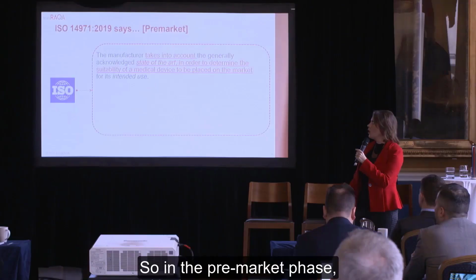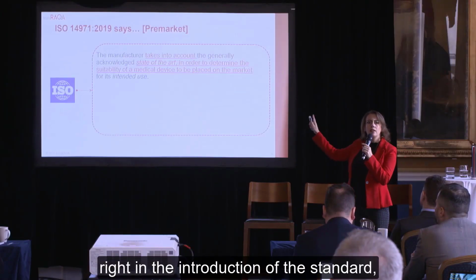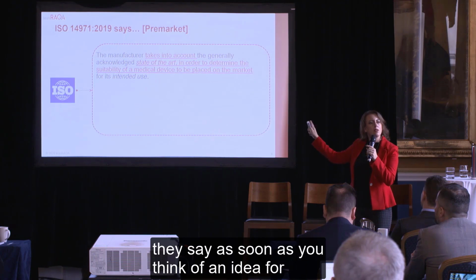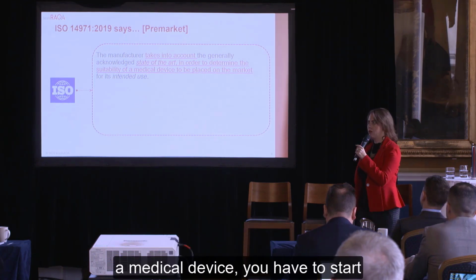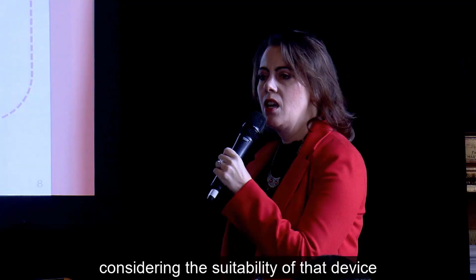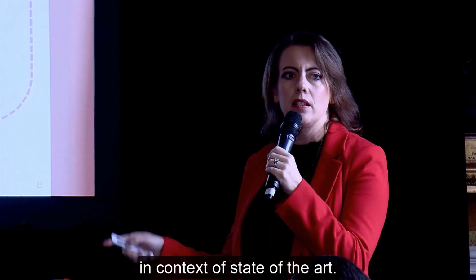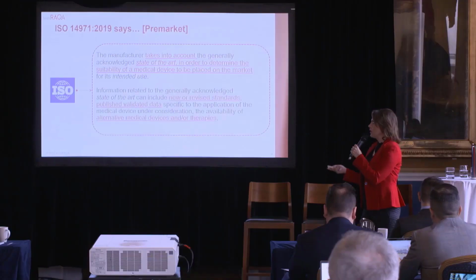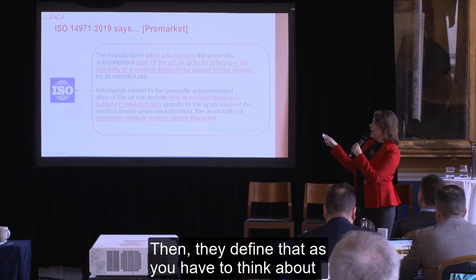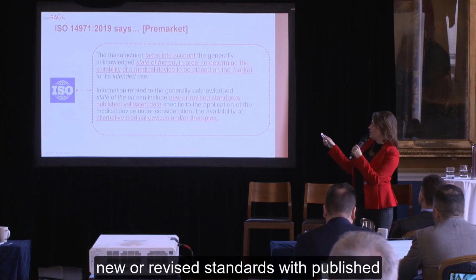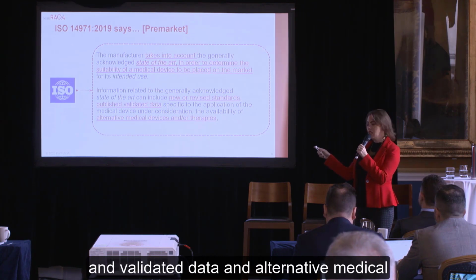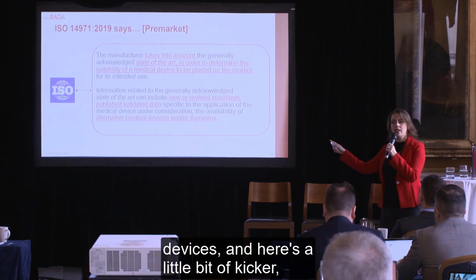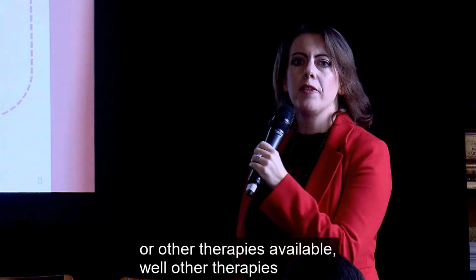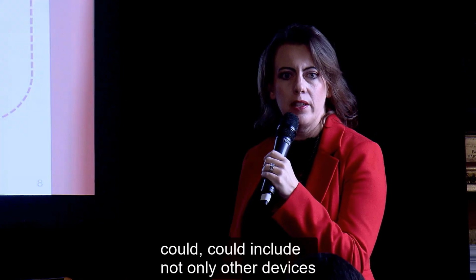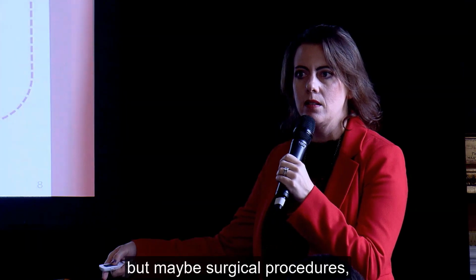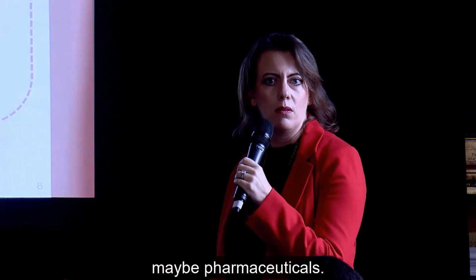So in the pre-market phase, right in the introduction of the standard, they say as soon as you think of an idea for a medical device, you have to start considering the suitability of that device in context of state of the art. Then they define that as you have to think about newer revised standards with published and validated data, and alternative medical devices, and here's a little bit of a kicker, or other therapies available. Well, other therapies could include not only other devices, maybe surgical procedures, maybe pharmaceuticals.